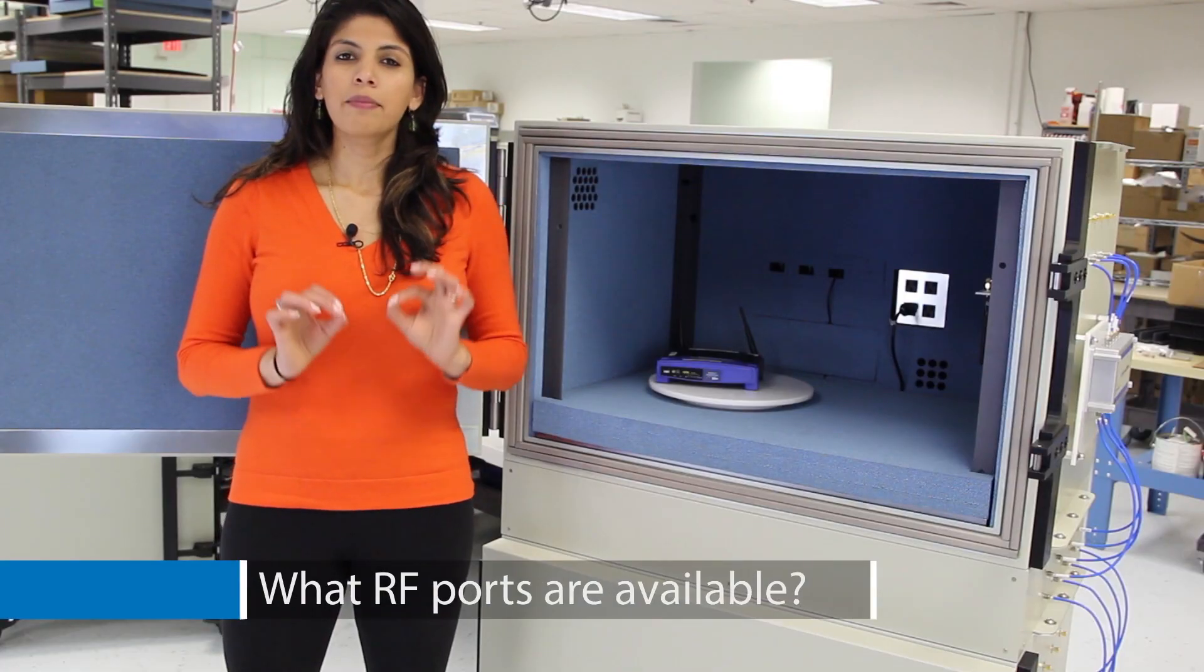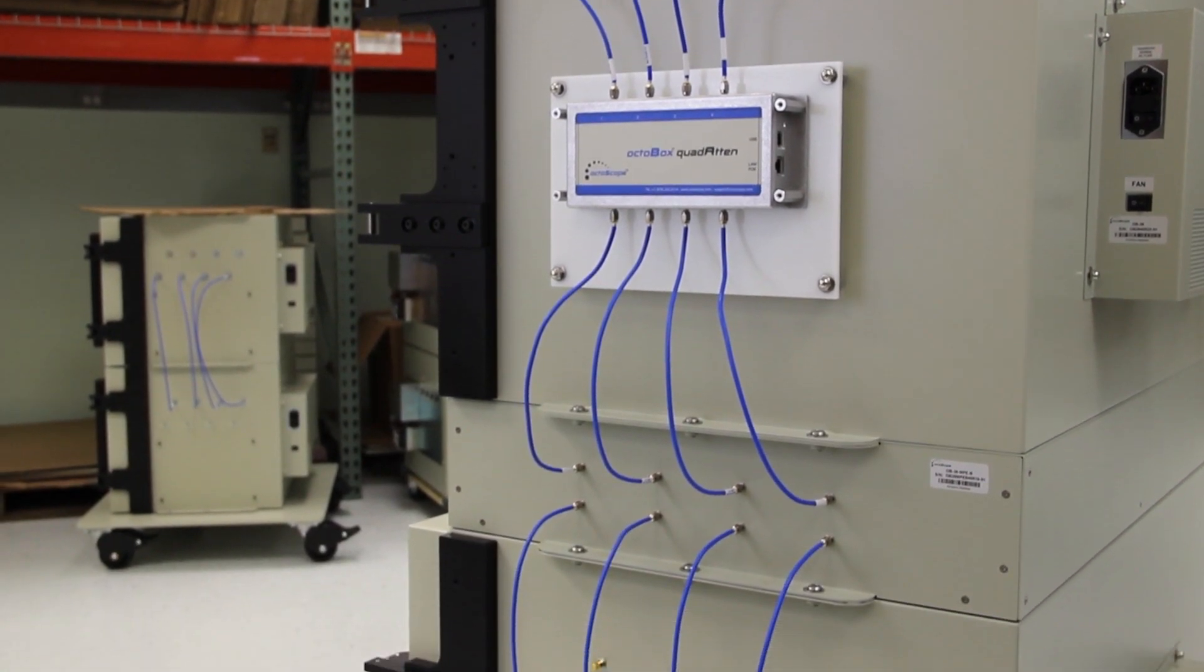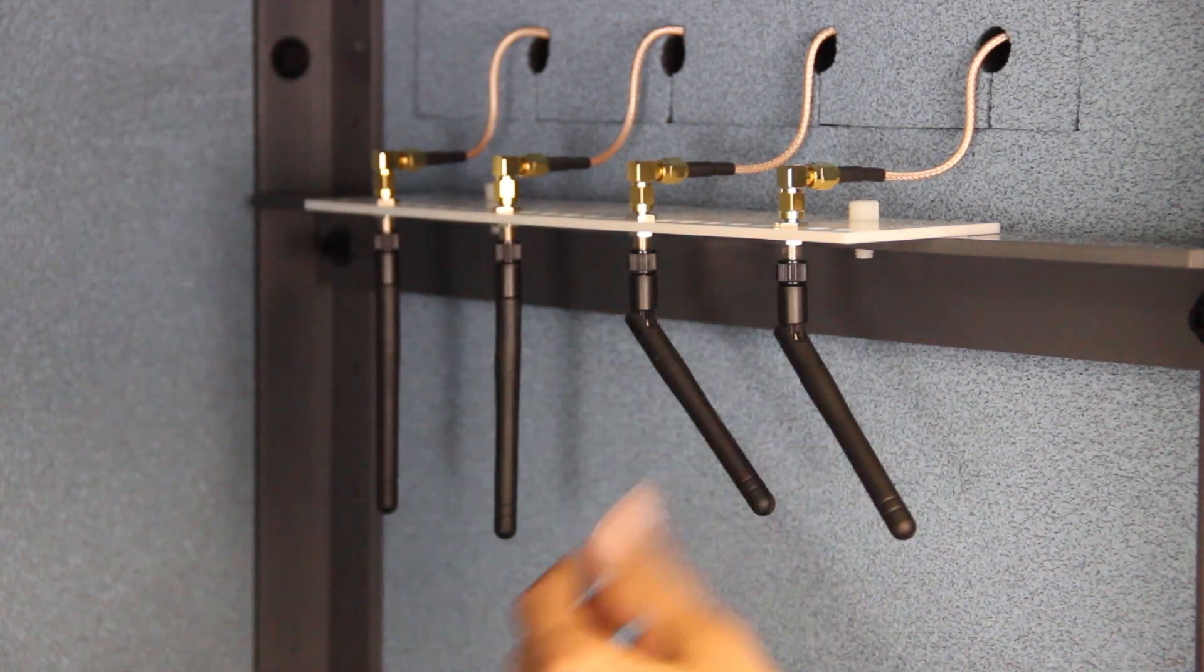Each octoBox comes equipped with 8 RF ports, either SMA or N connectors. Typically, 4 of the 8 ports are used for the 4x4 MIMO signal.